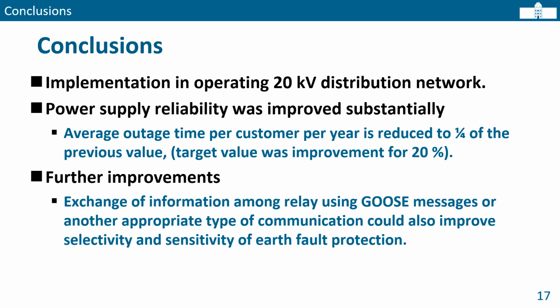Further improvements are possible with the introduction of communication and exchange of messages between individual relays. This is valid for the short circuit with the overcurrent protection, as well as for the earth fault protection. In the case that these communications were introduced, the presented overcurrent protection scheme will be used as a backup.